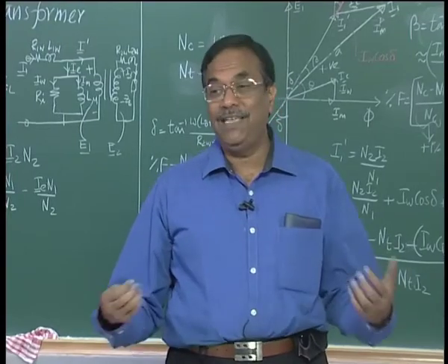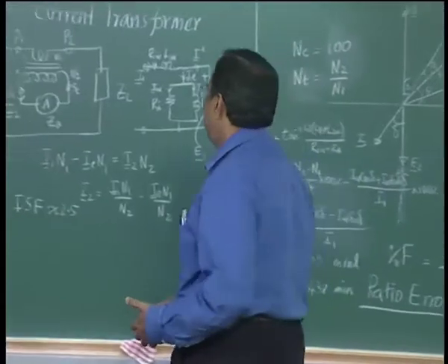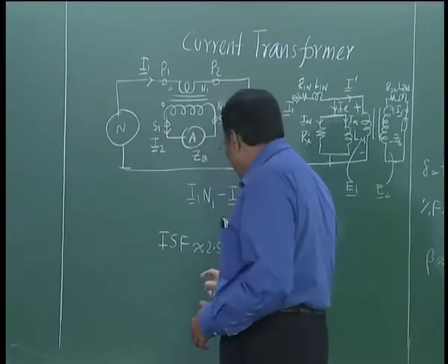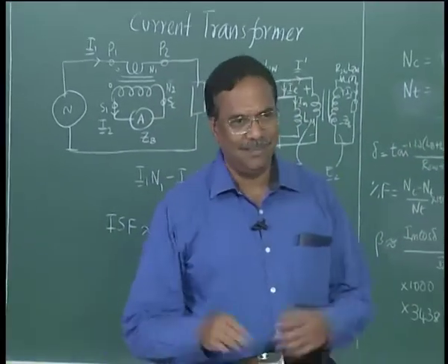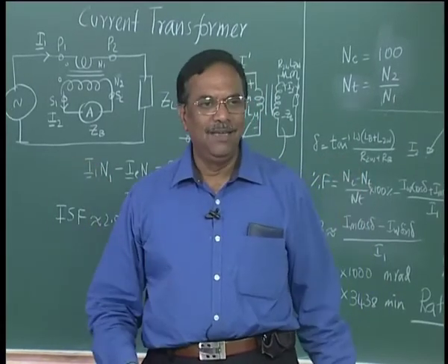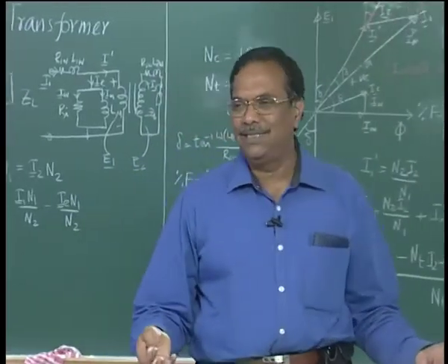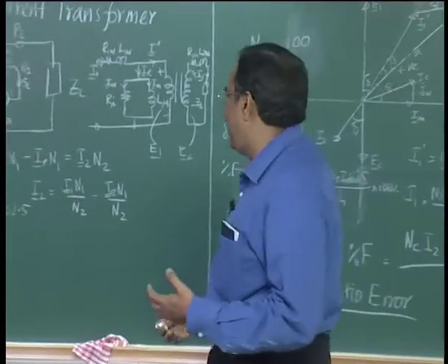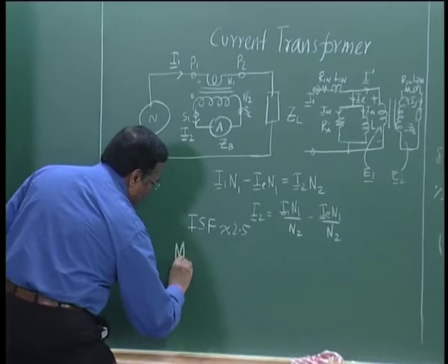I want to see whether a fault has occurred, right. Now when a fault occurs on the primary side, my secondary current is not going to give me a faithful reproduction of the fault current, right. Let us say fault current is 50 times, my secondary current maximum will go to 2.5 times, it does not reflect. Such current transformers we call measuring current transformers.